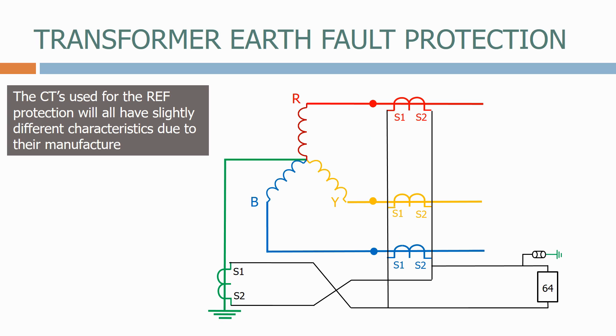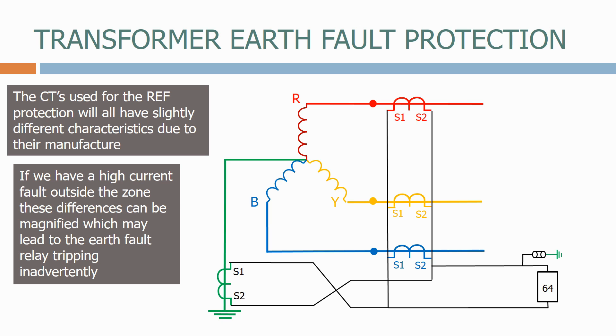The CTs used for the restricted earth fault protection will all have slightly different characteristics due to their manufacture. If we have a high current fault outside the zone, these differences can be magnified, which may lead to the earth fault relay tripping inadvertently.